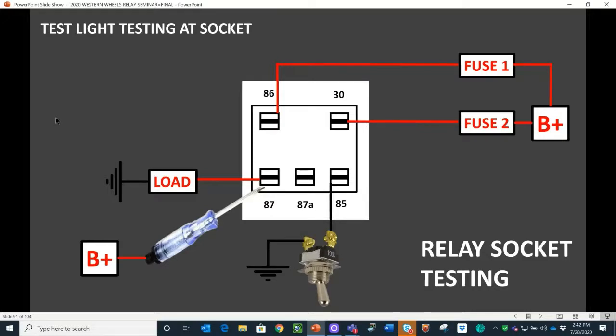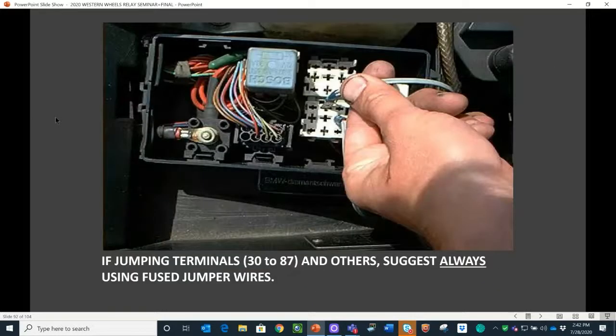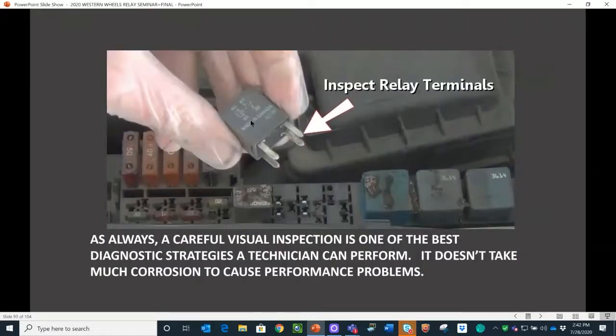And of course, just a reminder, when jumpering anything on a relay socket, always use fused jumper wires. Always add a careful visual inspection, one of the best diagnostic strategies. Inspect the terminals, inspect the socket, look for green, look for corrosion. It doesn't take much corrosion to cause circuit performance problems, because remember, we're dealing with milliamps here in the coil circuit. It doesn't take much to screw it up.